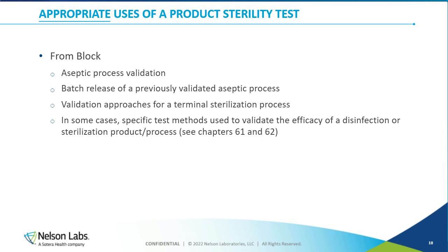And I should add, in the industry, we're trying to make it clear that it's not always terminal sterilization to 10 to the minus 6 or aseptic processing. There are documents in the industry to support that. Rather than saying we can't do 10 to the minus 6, let's just go to aseptic, an alternate SAL, for example, 10 to the minus 5, 4, or even 10 to the minus 3, still provides assurance of sterility that is actually more easily demonstrable than an aseptic process. So you could rationalize use of 10 to the minus 3, for example, for a terminal sterilization process, and still put sterile on the label rather than going with aseptic.